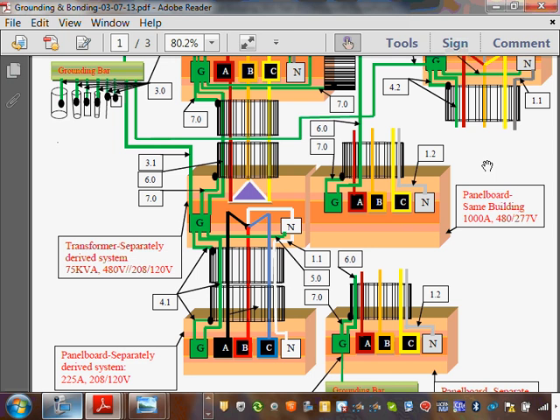There are multiple ways of doing this, guys. If you're building a steel building and your service is 500 feet away from where this transformer is located, you can just tie directly to the steel and you're bonded. Another option, if you have a water pipe in an industrial establishment, Jeff, you and I would do that one. You would take your transformer, one end, tie it to the water pipe, that continuous, clear, you can see it. At one end, tie the transformer to it. The other end, the service tied to it, and that will bond the two together.